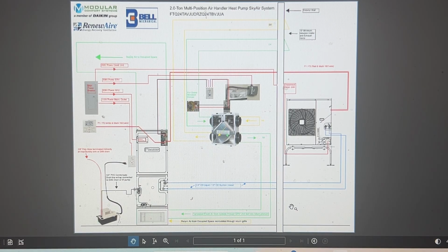So to break this down, I create these drawings for my installation team so that they can check the boxes on what we've got to get done and make sure that we have a complete system before moving on to the next unit. So I'd like to describe a few things that go into making this complete. We have a forced air handler down here. On this particular project, it was sitting on a concrete pad in the basement. There is an outside condensing unit, which is here. That sat on a concrete pad on the rear of the townhome. And then there's the energy recovery ventilator here, which was down in the basement as well. That was a wall mount.